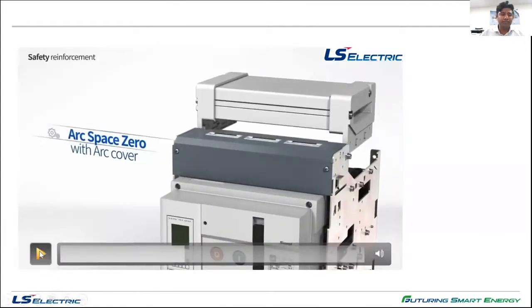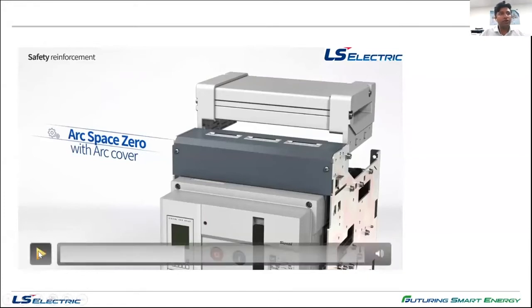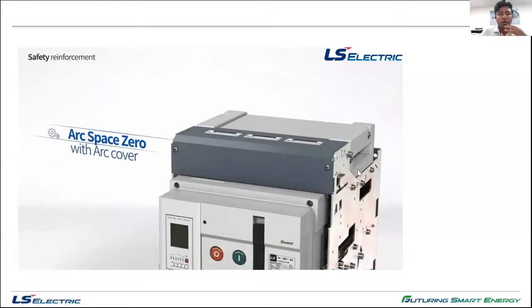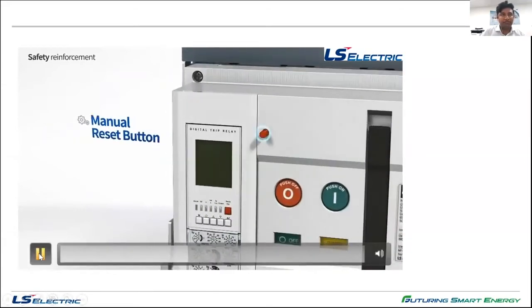Safety and reliability: there are certain optional accessories which come as standard in Susole and as an optional accessory in Metasole. For example, the zero arc space cover. The use of the zero arc space cover is if you have a couple of ACBs to be mounted with minimum distance, or when you want to run a live bus bar without enough clearance from the air circuit breaker, then you can use a zero arc space cover. This allows you to mount a live bus bar or an ACB without a minimum clearance distance.